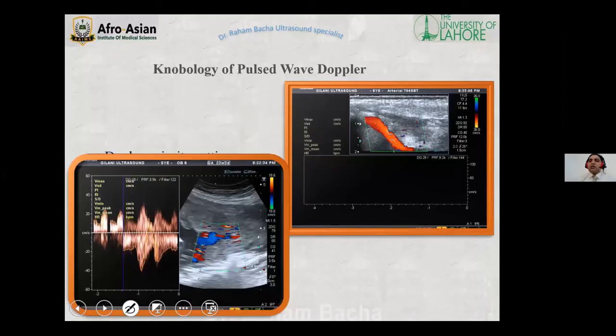Then we have duplex priority setting, on some of the machines. Whenever we are performing a grayscale ultrasound, the transducer is performing one work. Whenever we superimpose color Doppler on it, now the transducer is doing two works. And whenever we superimpose spectral Doppler on it, now the transducer will perform three works at a time, and its efficiency will reduce. So for improvement in the efficiency of the transducer, we have to select some duplex priority setting.